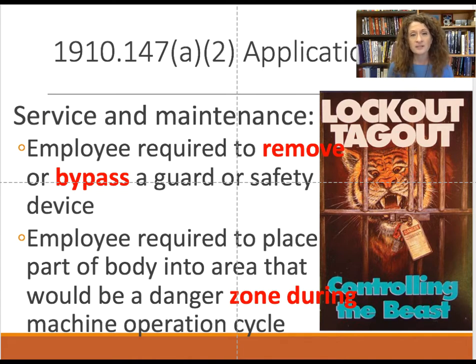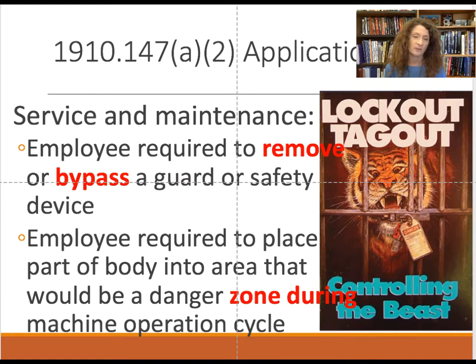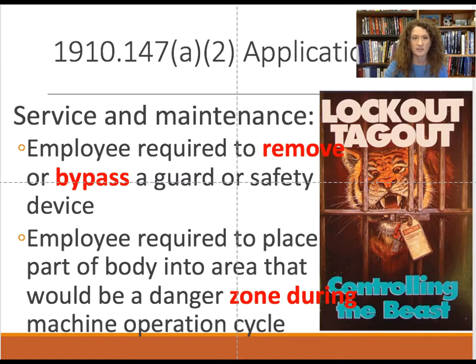Lockout-tagout applies to service and maintenance — specifically when employees are required to remove or bypass a guard, or when employees put a body part into a danger zone where they can be pulled in, electrocuted, or must bypass a guard to perform the operation. That is when lockout-tagout is necessary.